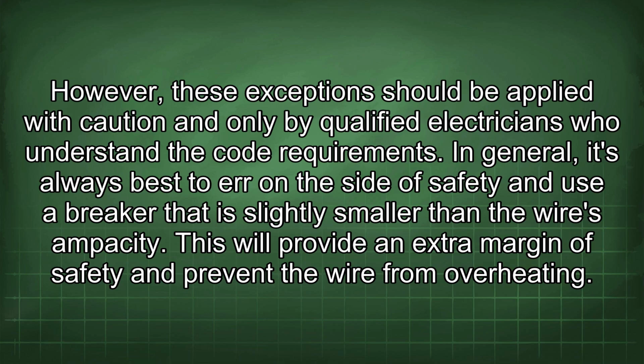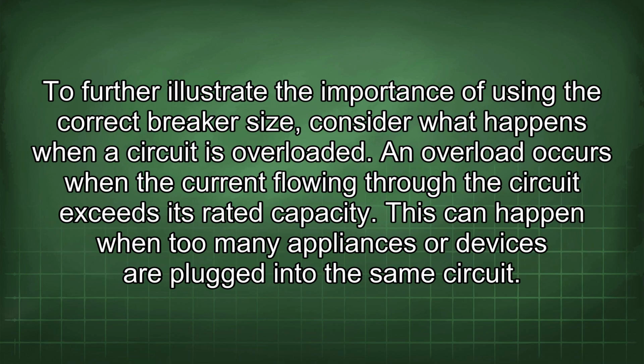In general, it's always best to err on the side of safety and use a breaker that is slightly smaller than the wire's ampacity. This will provide an extra margin of safety and prevent the wire from overheating. To further illustrate the importance of using the correct breaker size, consider what happens when a circuit is overloaded. An overload occurs when the current flowing through the circuit exceeds its rated capacity.